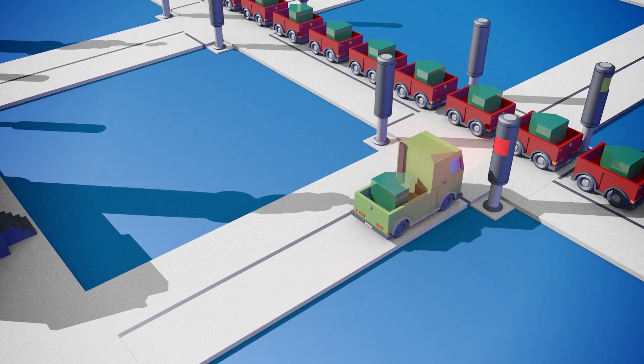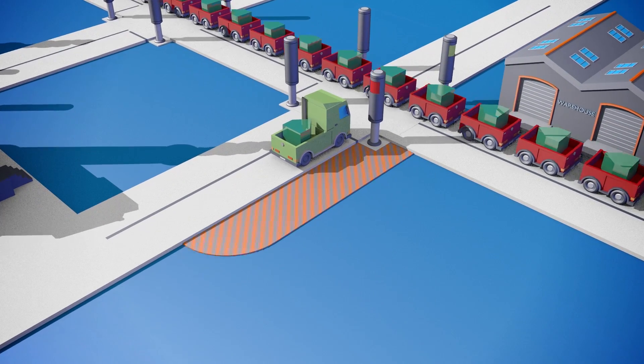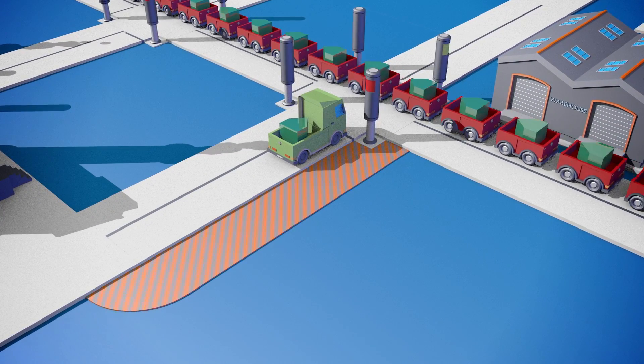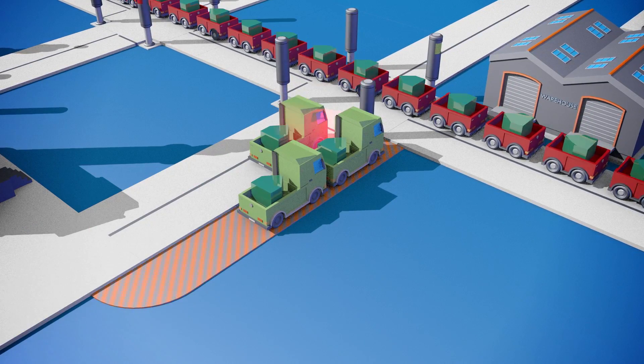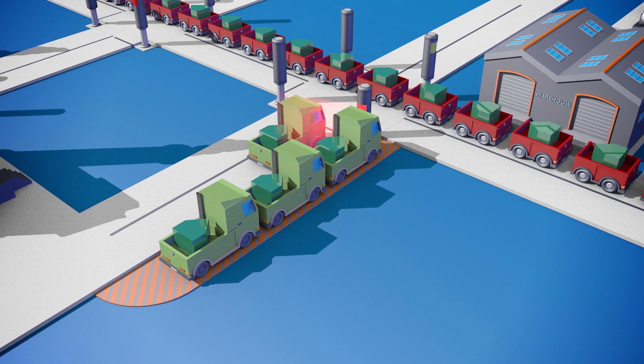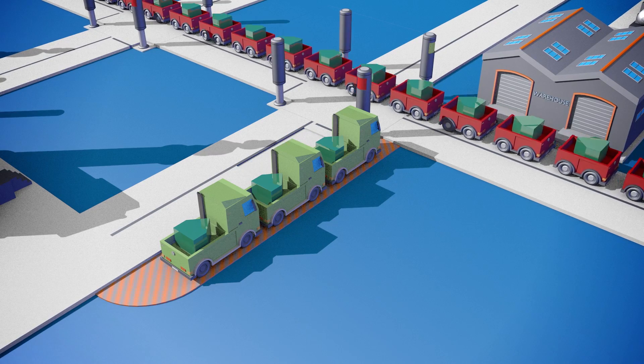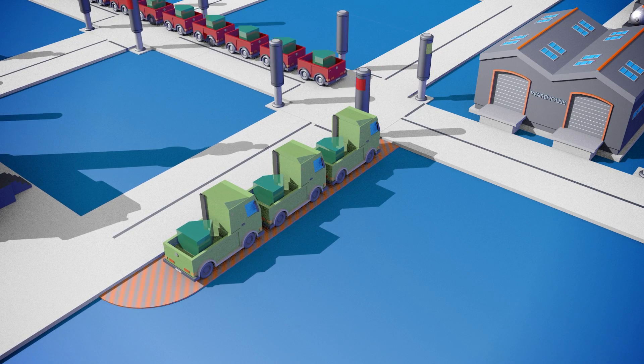This heavy load affects the behavior of the switches. Each switch has memory capacity, so-called queues. When traffic is heavy, the queue provides interim storage for the telegrams. If the load remains high in the long term, the queue becomes full and all new incoming messages are lost. These so-called discards are a sure sign of unstable communication operations.